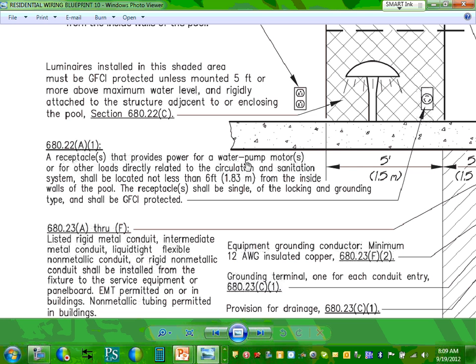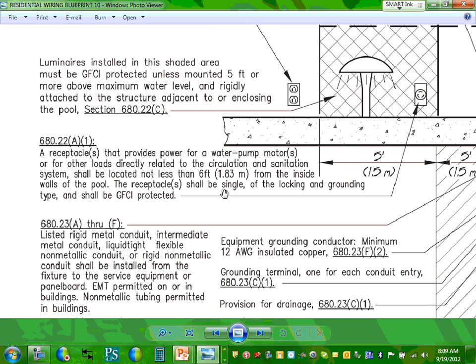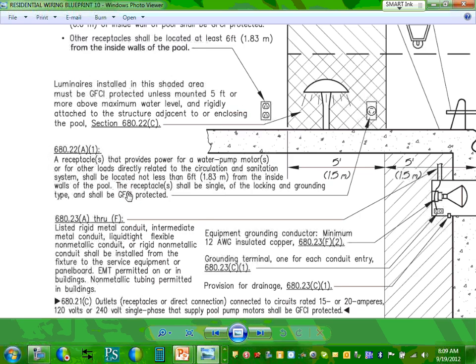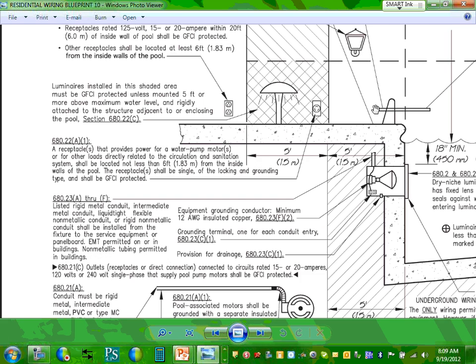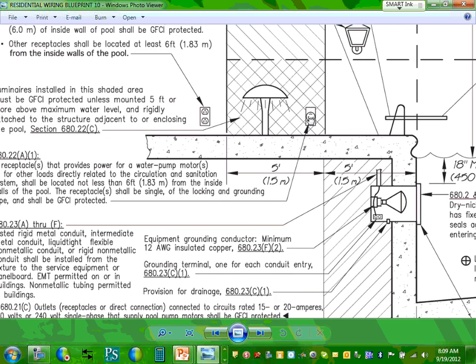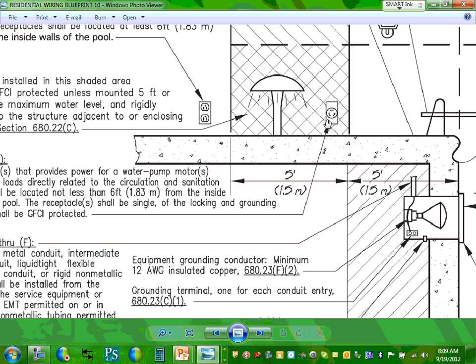Receptacles that provide power for the water pumps shall be located not less than 6 feet from the inside of the swimming pool. Receptacle shall be single or locking and GFCI. This is for storable receptacles and storable pumps. You have a receptacle, you're plugging the pump into it.